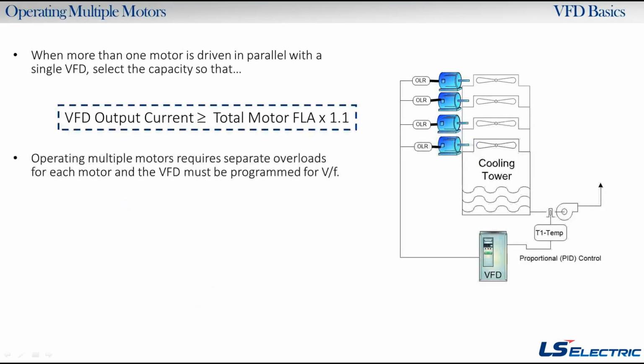So another question that comes up about motors is, can we run multiple motors off of one drive? Yes, we can. There's no problem with that. You just want to run them in parallel. And one of the advantages of that is you have just one drive. So you can have one big drive that's like 100 horsepower, and you can have it run like 10 smaller, 7.5 or 10 horsepower motors. You can run like 10 of those.